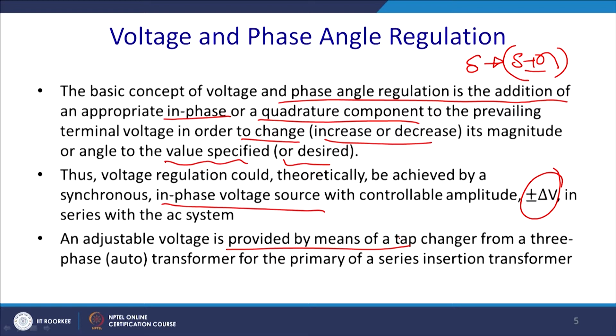An adjustable voltage is provided by means of a tap changing three phase autotransformer for the primary series injection or insertion transformer. We shall see this circuit here. So, this is the in-phase voltage regulator. You have the step changing autotransformer, from there you tap and ultimately add a voltage in phase. The transmission capability increases, and in the same way you can reduce it. So, you can add delta VA, delta VB and delta VC. For this arrangement, it is evident that the injected voltages delta VA, delta VB and delta VC are in phase with the line to neutral voltages VA, VB, VC. So, you can have a voltage regulator which can inject or take out voltage in the same phase.